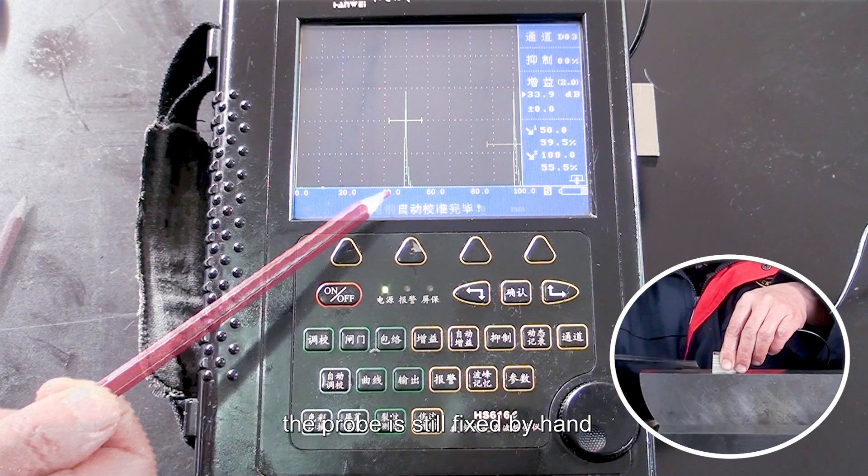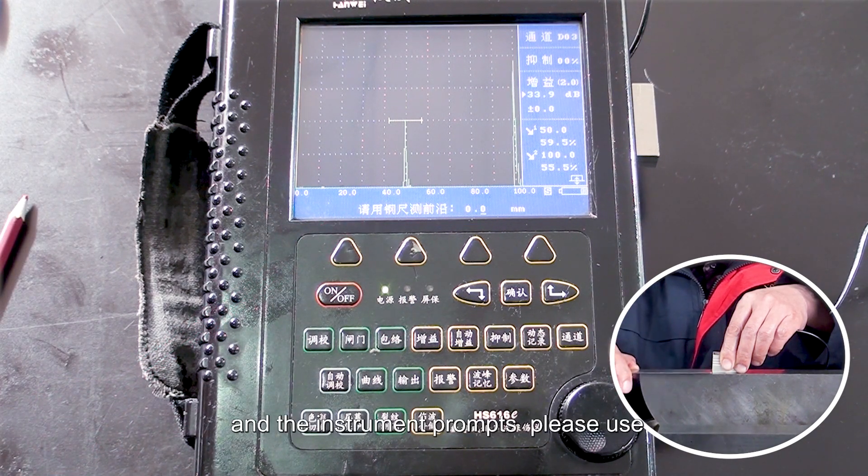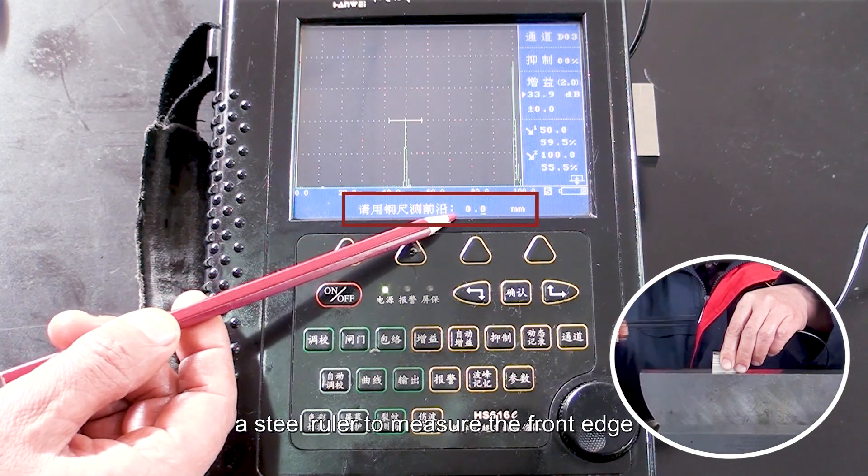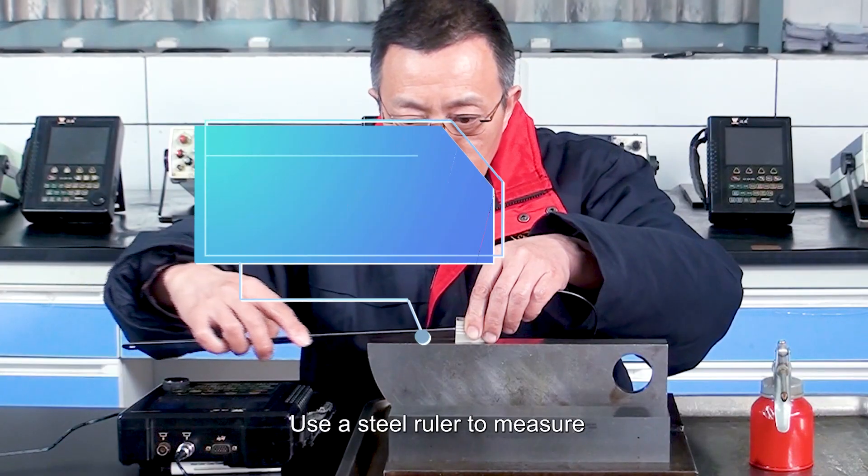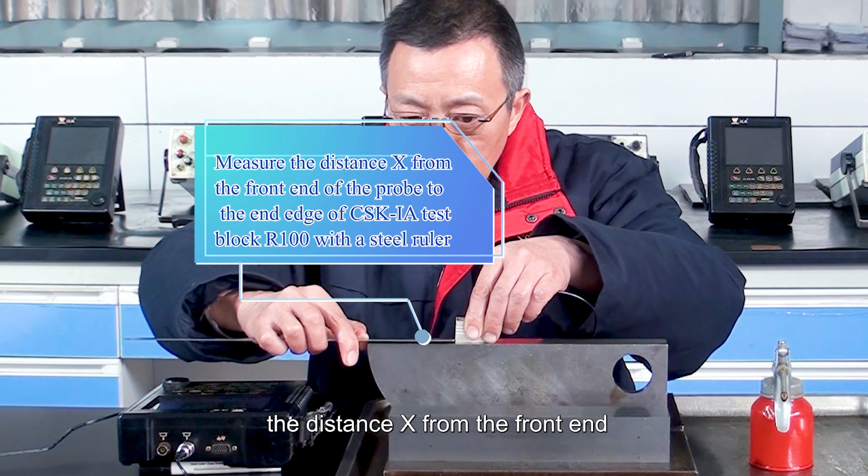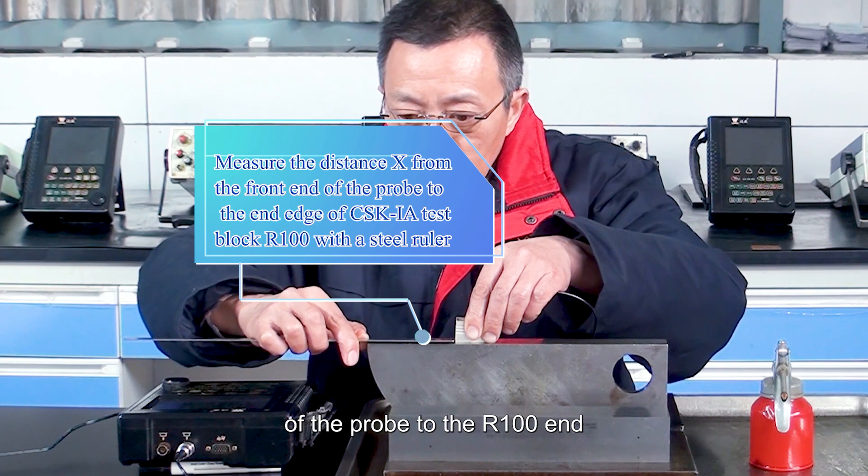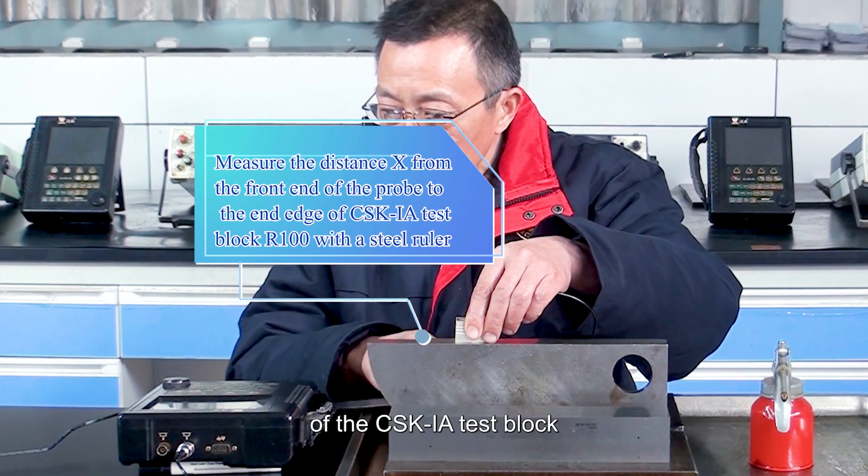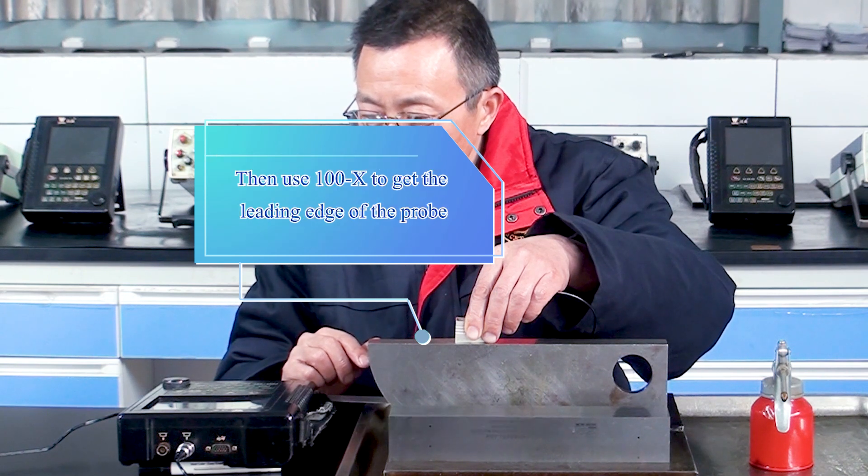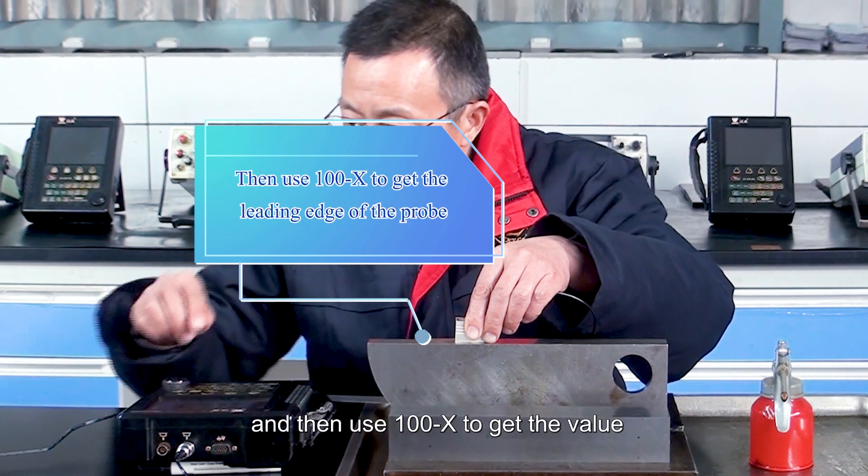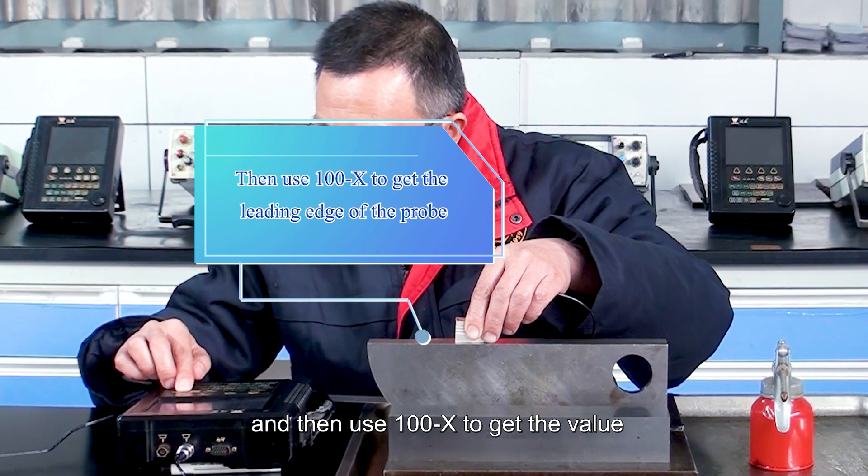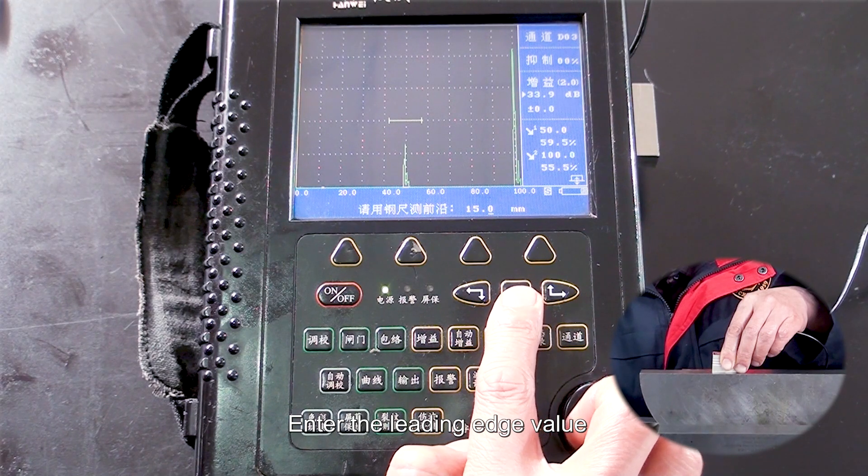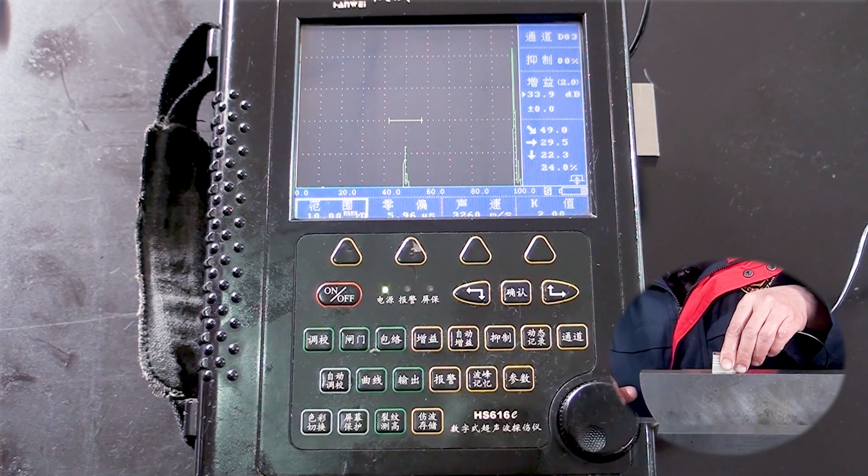After that, the probe is still fixed by hand, and the instrument prompts, please use a steel ruler to measure the front edge. Use a steel ruler to measure the distance x from the front end of the probe to the R100 end of the CSK-IA test block. And then use 100-X to get the value of the front edge of the probe, enter the leading edge value, and press the OK key.